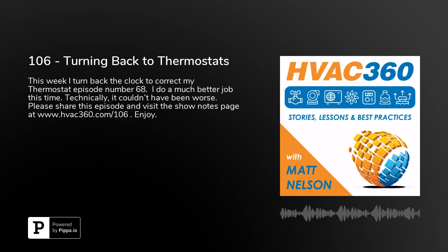So if the room, for example, was set to 70 and all of a sudden it didn't have this cooling effect, and the sun hit the room and it started heating up, it would go from 70 to say 72. So if you have 2 degrees, you have 68 to 72. You go up to 72 and it'll start cooling. It'll turn off all the heating, the auxiliary heating, all the reheat, and it would start opening up the cooling valve, the air valve, and just flooding the room with cooler air. So it would cool it down to 70, and then it would stop. But if you're in that constant heat gain mode, it'll heat up again and you're cooling it off. So it cycles between when it will turn on and when it'll turn off.